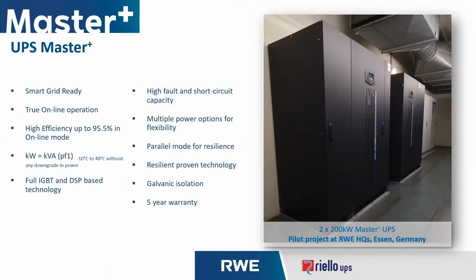The UPS system specifically developed for this project had to meet certain criteria. First, the system had to be smart grid ready, which effectively means that the UPS system can be installed and operated in a smart grid environment. The system had to operate in true online mode with a high efficiency of 95.5%. The output power of the UPS system needed to be unity, meaning the output kVA rating of the UPS matched that of the kilowatt rating, even during low and high operational temperatures.